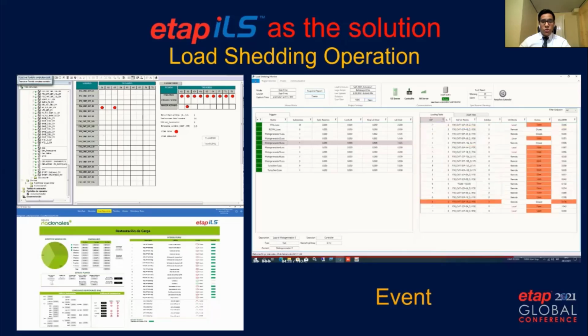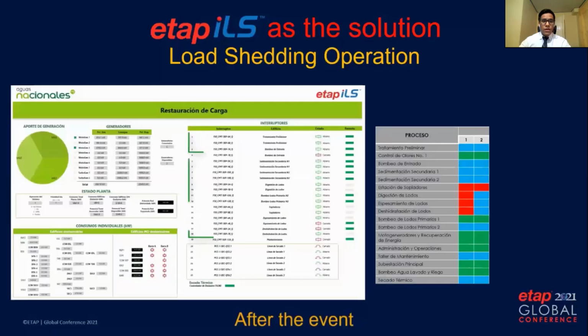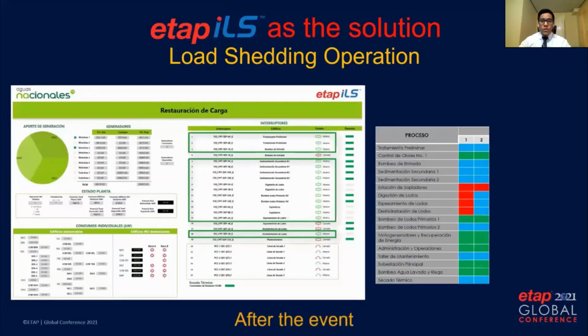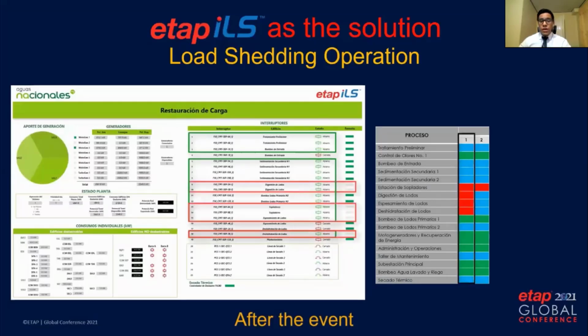Now let's see what happens when the event occurs. The loads are shed by the PLC from the system according to the trip command list. Then ILS calculates the new requested load to be shed based on the generation of the power units that are still online and the new available loads. The offline loads can be restored depending on their control mode and interlocks. Now, let's get closer to the operator view. Here we have all the green loads offline, but the critical process is still online, while 2 motor generators are supplying the power that the system is requesting. For the restoration of the system, the loads in red are locked by the PLC logic, and the other loads are available for being restored.